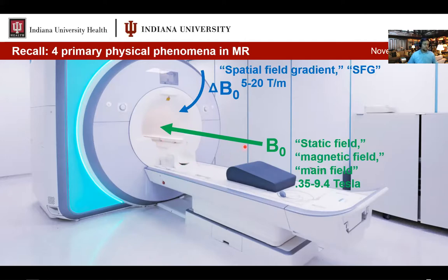If you're going to approve someone to go in with a device that has a specified maximum spatial field gradient that is below the maximum field gradient of your scanner, you need to think very carefully about how you're going to ensure their safety and ensure that they do not cross that line. A lot of times we'll have technologists or MRSOs call the MR physicists, and we'll actually examine the device with the technologist and come up with a plan for how best to get them in and out of the scanner safely if they must go in. The best way of dealing with this, of course, is to find a scanner that has a lower maximum field gradient and allow them to be scanned.